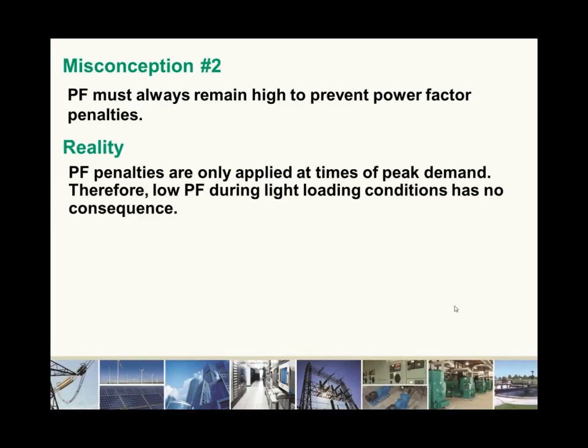So misconception number 2 is that power factor must always remain high to prevent power factor penalties, when in reality power factor penalties are only applied at times of peak demand. Therefore, low power factor during light loading conditions has no consequence.